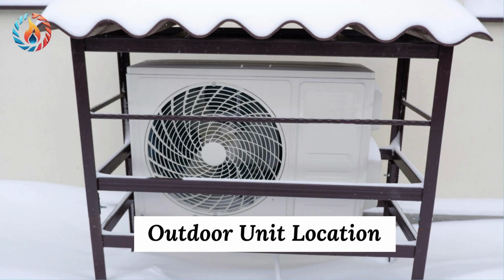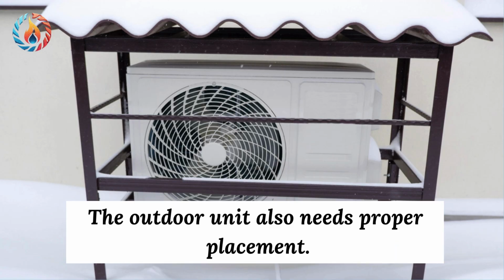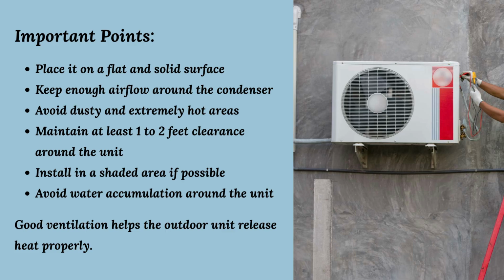Outdoor unit location. The outdoor unit also needs proper placement. Important points. Place it on a flat and solid surface. Keep enough airflow around the condenser. Avoid dusty and extremely hot areas. Maintain at least 1 to 2 feet clearance around the unit. Install in a shaded area if possible. Avoid water accumulation around the unit. Good ventilation helps the outdoor unit release heat properly.